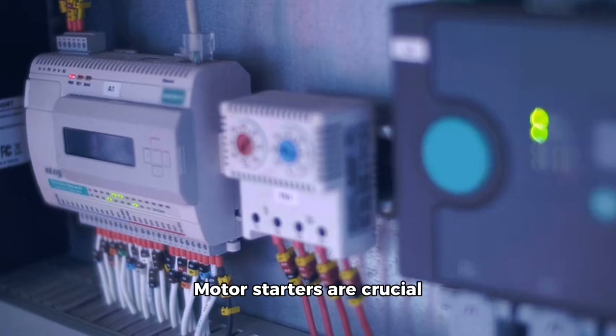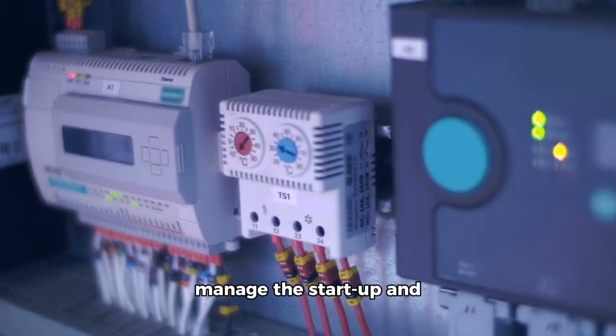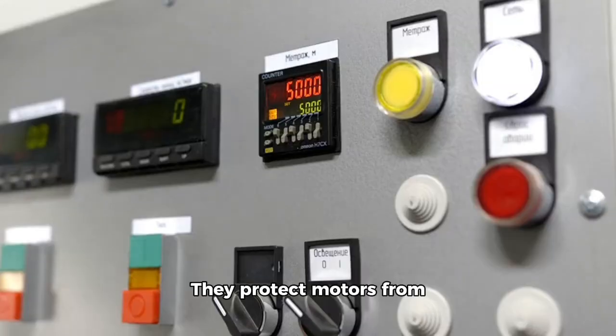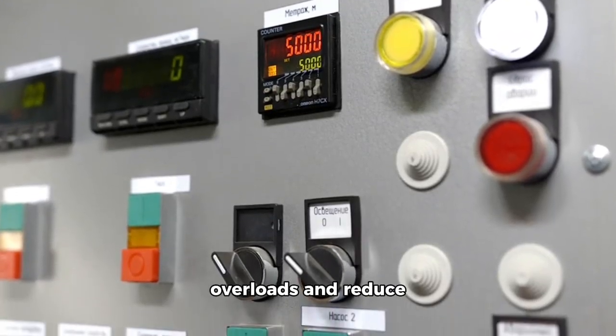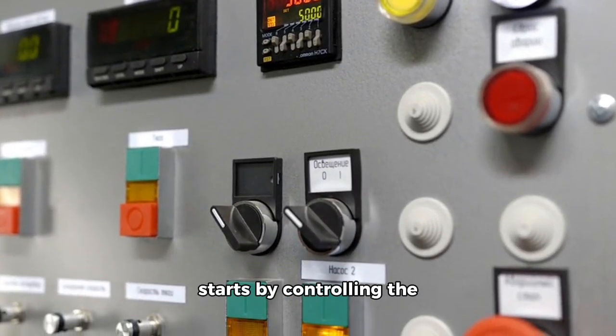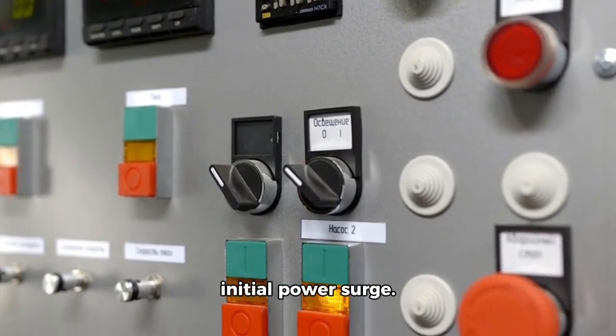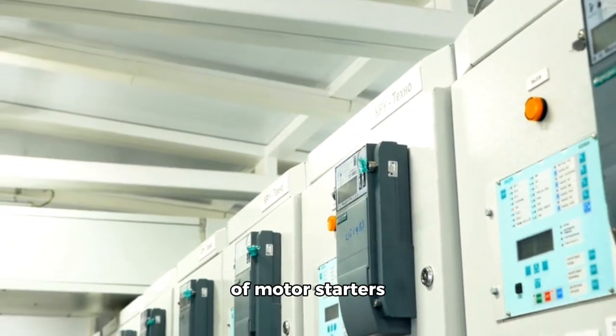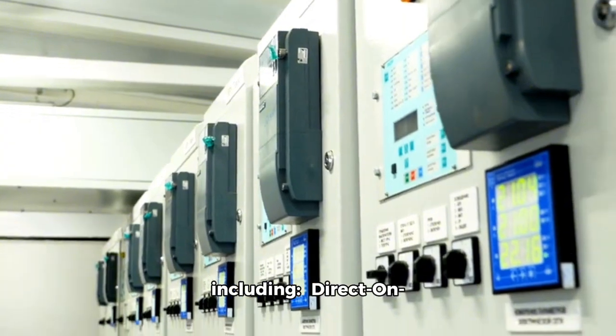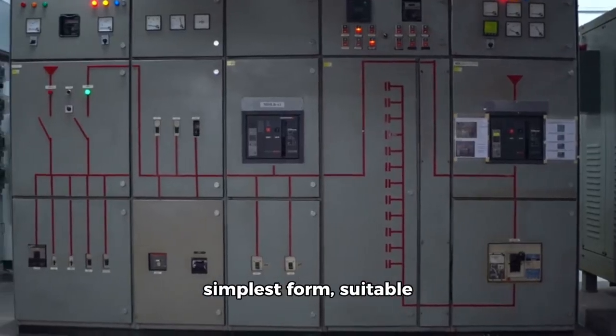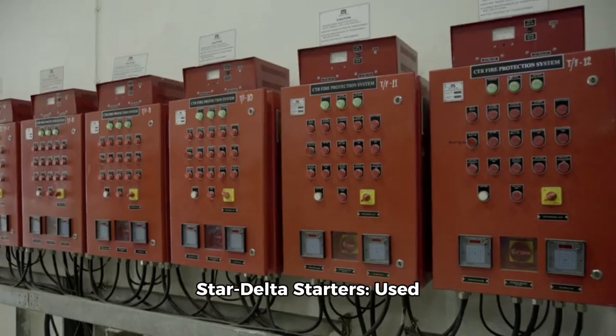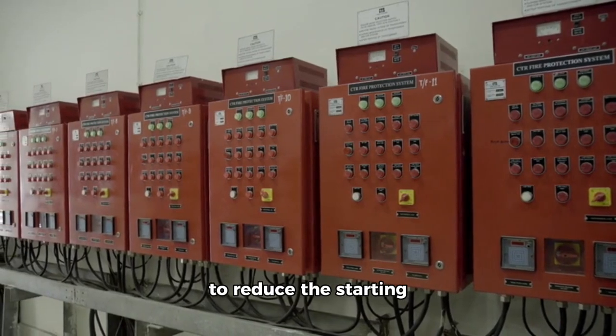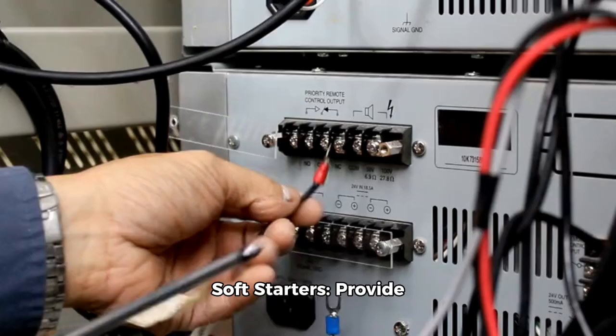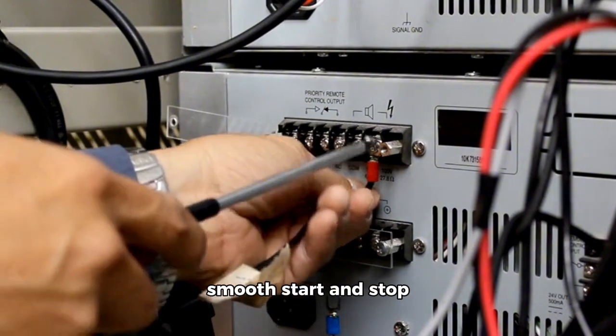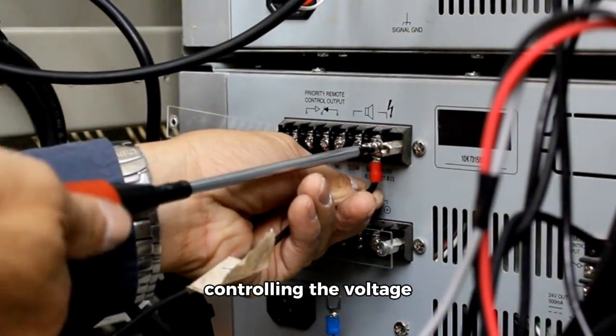Motor starters. Motor starters are crucial devices used to safely manage the startup and shutdown of motors. They protect motors from overloads and reduce electrical stress during starts by controlling the initial power surge. There are several types of motor starters, including direct online (DOL) starters, the simplest form, suitable for small motors. Star-Delta starters are used to reduce the starting current of larger motors. Soft starters provide smooth start and stop operations by controlling the voltage supply to the motor.